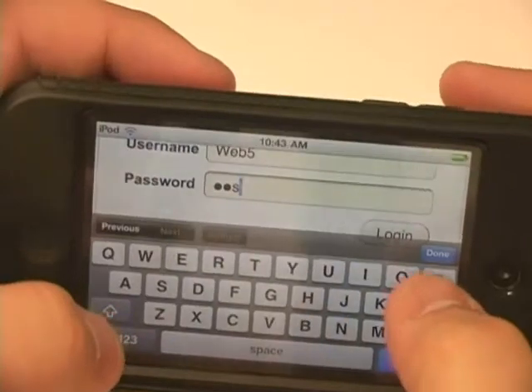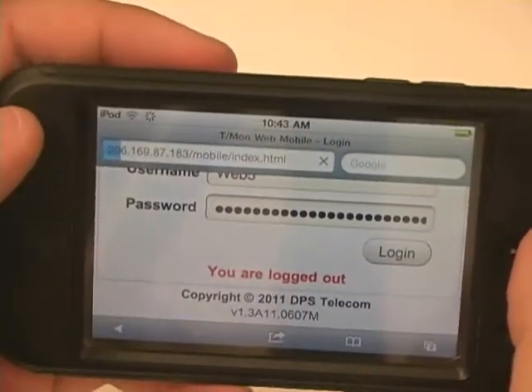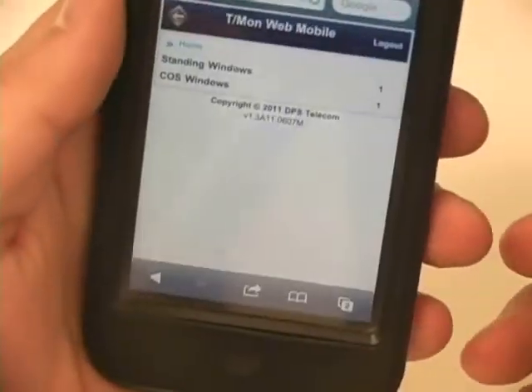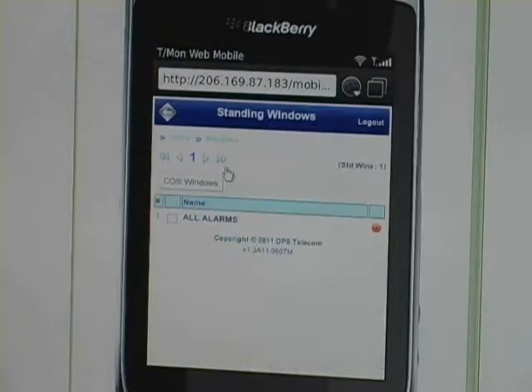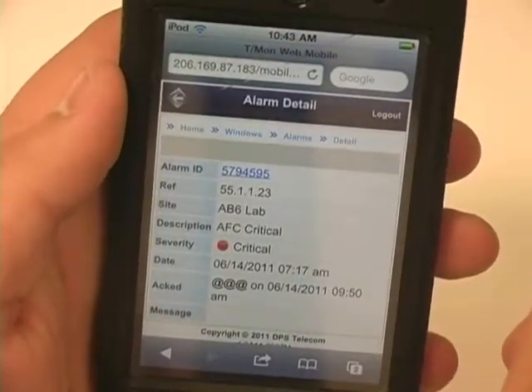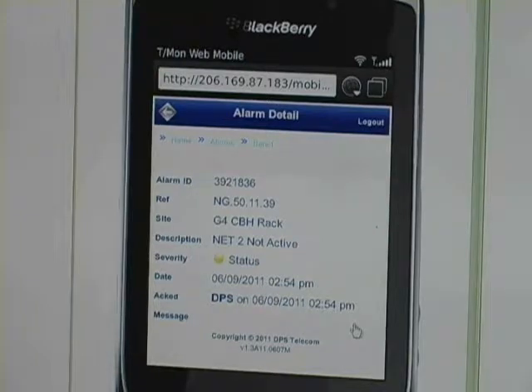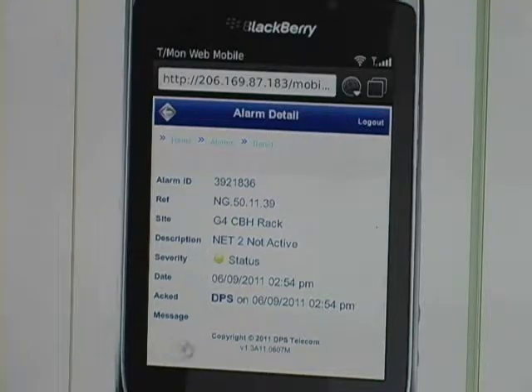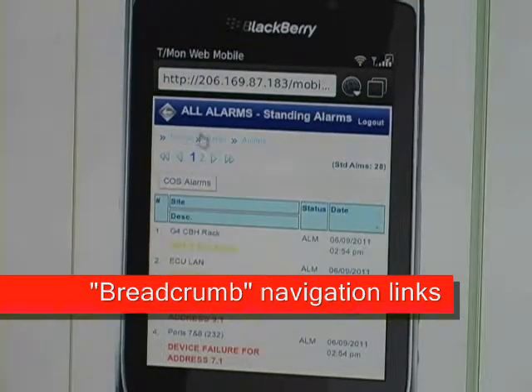So let's take a look at the login screen with the iPhone. Once you're logged into the T-Mon interface, you'll see standing windows or COS windows if you want to view standing alarms or change of state events. Here I'm clicking on standing windows and going into the all alarms window. You can see I can scroll through my various alarms, and I'm going to click here on AFC critical. This is the detail for that alarm point — things like alarm ID, what site it is, the description of the alarm, its current status, and also near the bottom is who acknowledged the alarm. Breadcrumb navigation links along the top of the page make it easy to navigate back up after you've drilled down to get alarm detail.